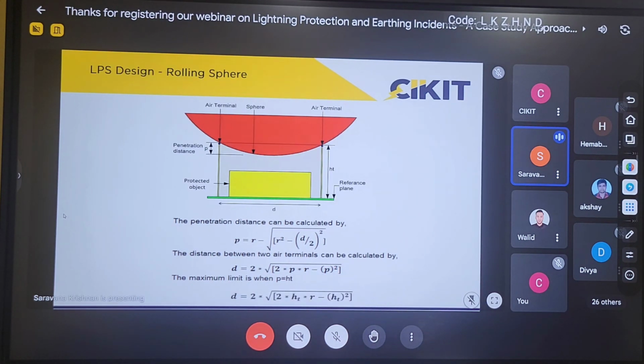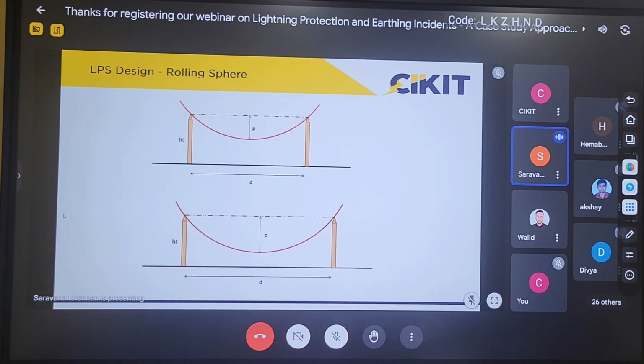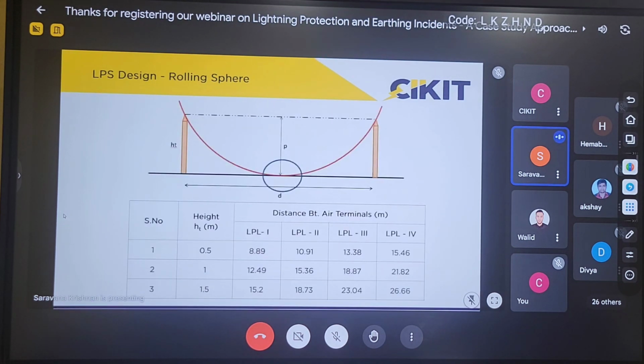If I increase the distance, the penetration distance also increases. If I increase it further, then at one particular point, what happens? The sphere will make contact with the structure to be protected. So here you can observe, if I increase the space between the air terminals, more portion of the sphere will come below the air terminal. If I increase further, then the center point will make contact. If the center point makes contact, then that particular portion will be considered unprotected.